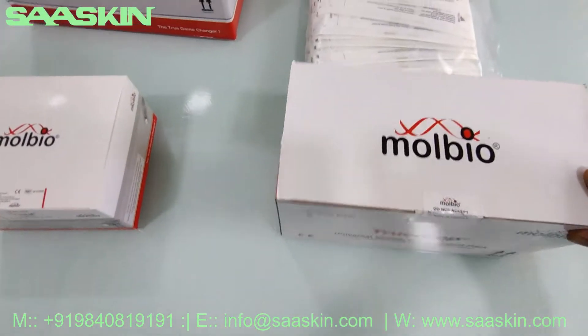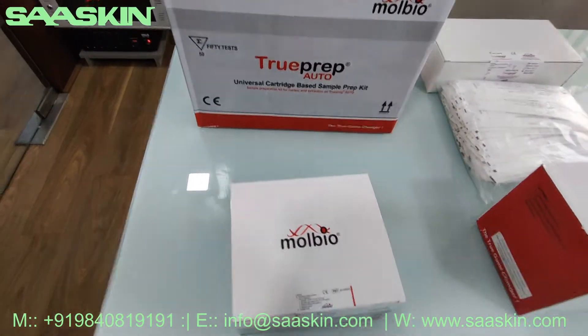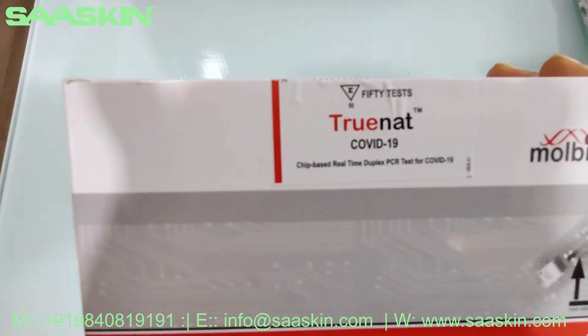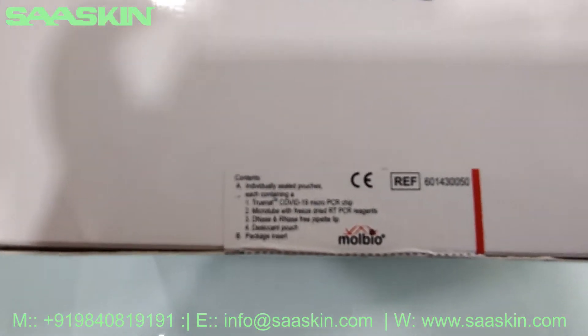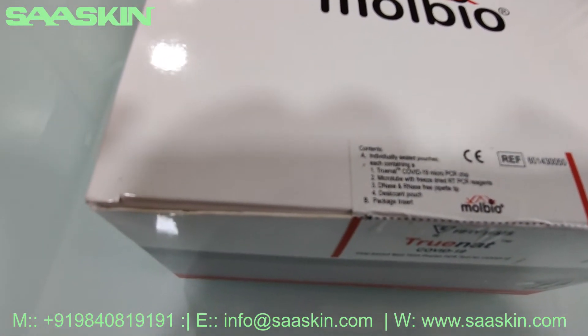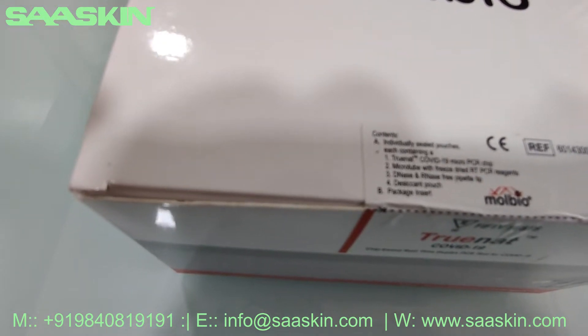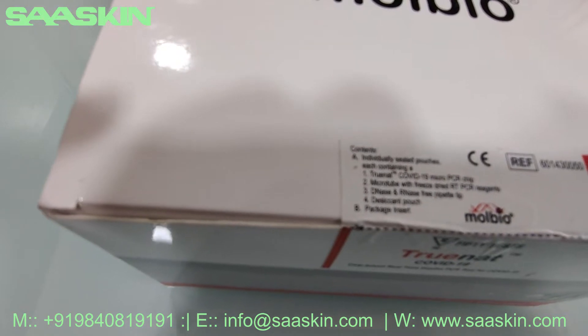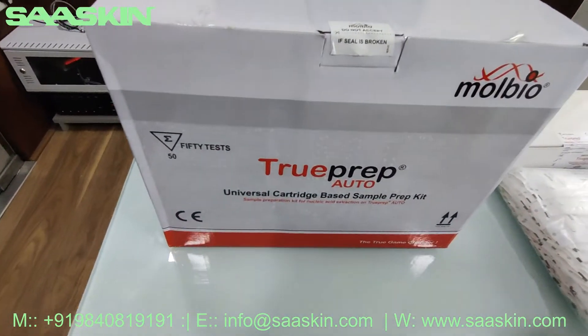Next I would like to introduce the chip used for this testing, which is the 50-number COVID chip. The contents of this chip box include individually sealed pouches, each containing a TrueNat COVID-19 micro PCR chip and a micro tube with freeze-dried RT-PCR reagents and DNase & RNase-free pipette tip, and a desiccant pouch.